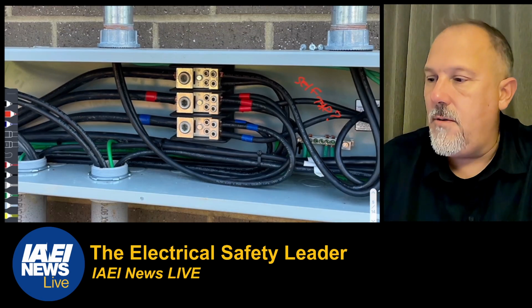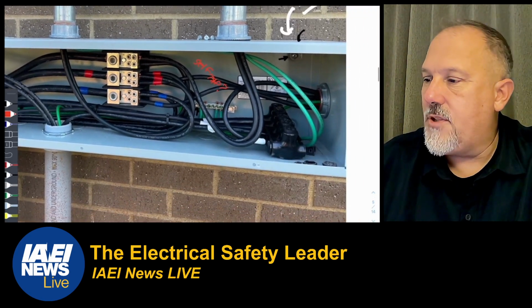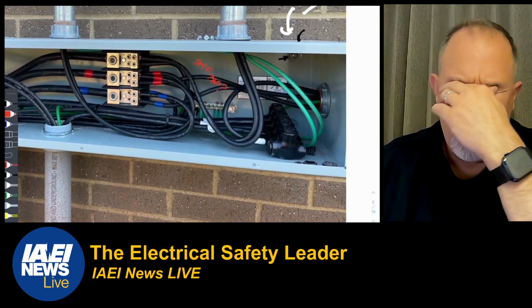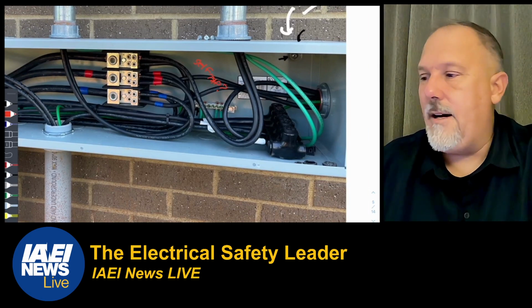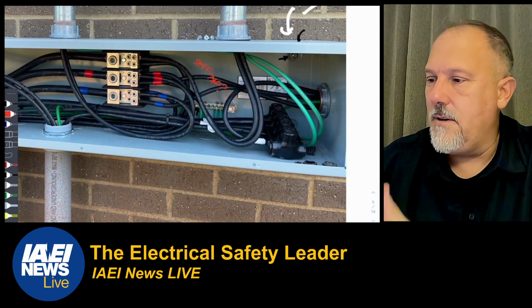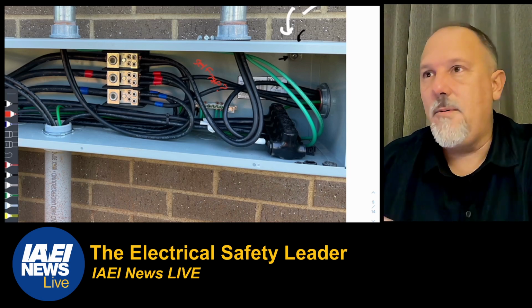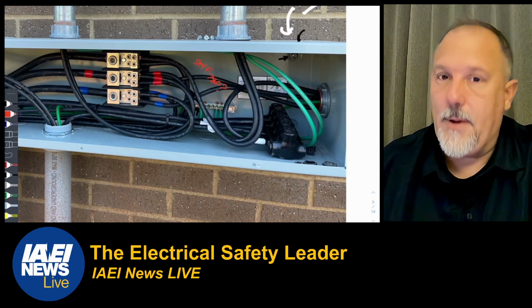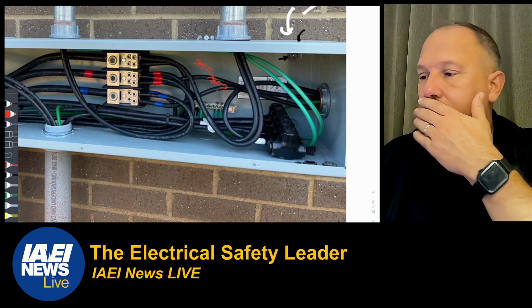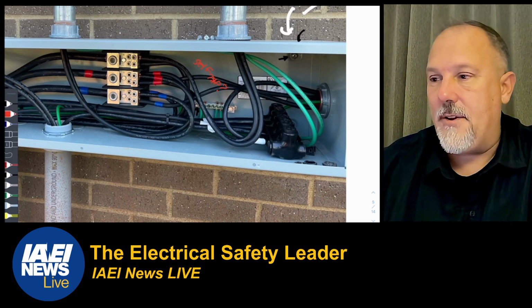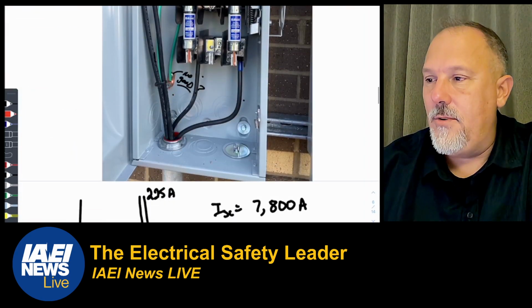Right? So in the trough, there's my three-phase conductors going into these power distribution blocks. And then my neutral comes over to this Polaris, or multi-tap, whatever. I think I just call them a Polaris, but I don't know if that's a brand name. But anyway, all of my neutrals are tied together. Now, what they did not do, there's the switch. This is the 100 amp switch.